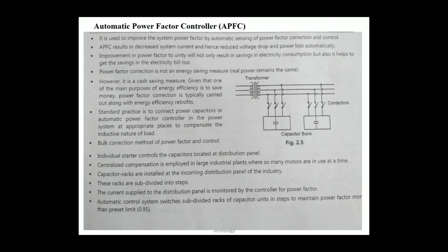The current supplied to the distribution panel is monitored by a controller for power factor. The automatic control system switches the subdivided racks of capacitor units in steps to maintain the power factor above the preset limit, that is 0.95. In this figure, the first is a transformer, that is a step down transformer, with R, Y, B. Then this RYB is connected to the capacitor bank.